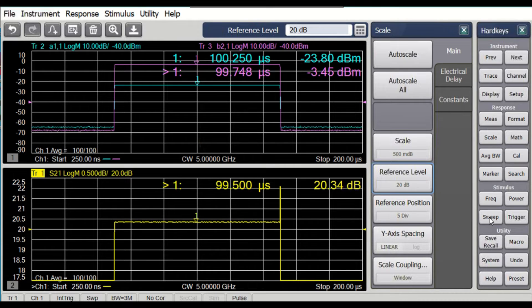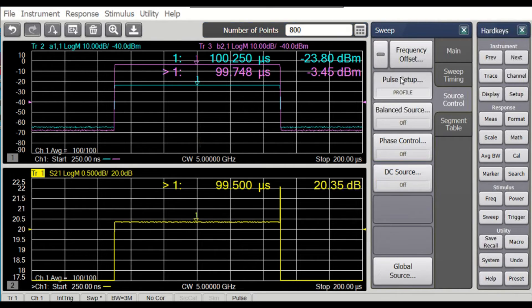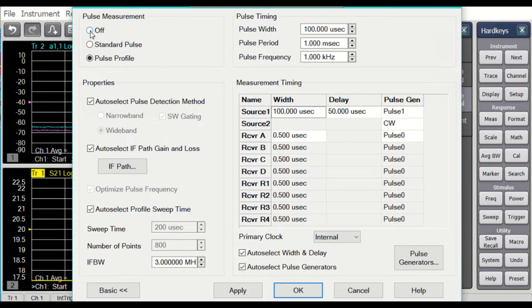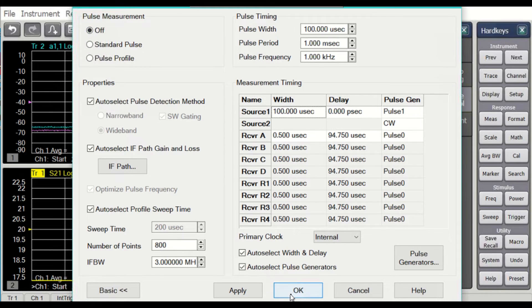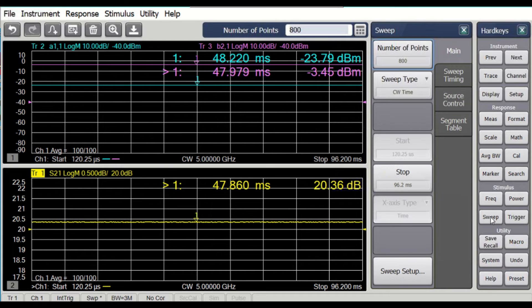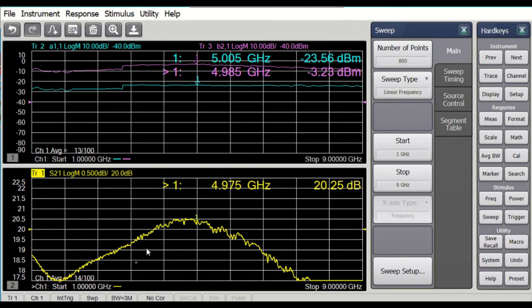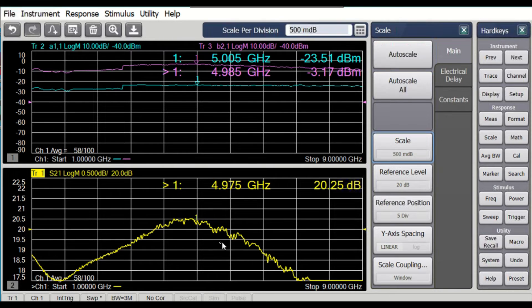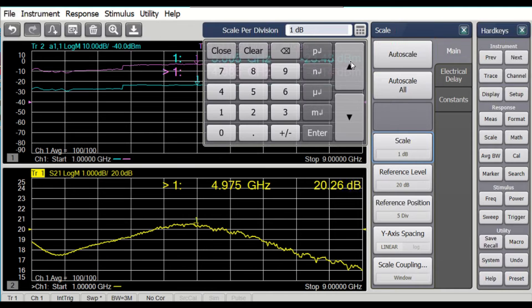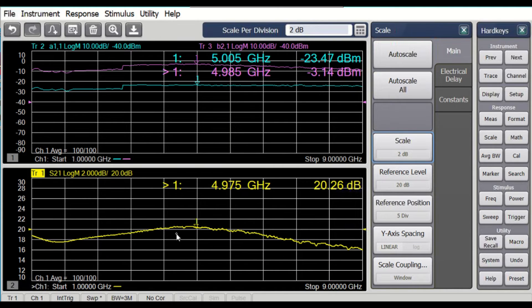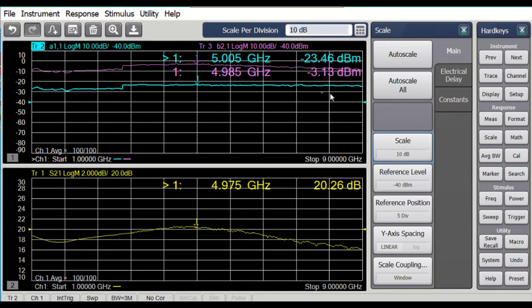Let's go back and look at another measurement — sweep, source control. Instead of the pulse profile, let's turn the pulse measurement off, and we'll change our sweep type back to linear frequency. Here we can see the S21 gain. Right now I'm uncalibrated, and we'll stay uncalibrated until we're ready to make a calibration.